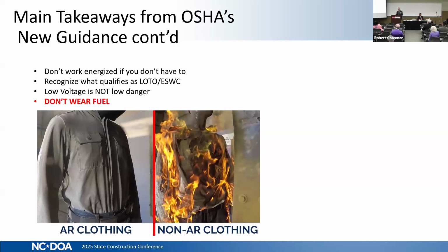So that's what you see on the slide. That's in the OSHA guidance. Every day, this should be daily wear for your workers that are working on electrical equipment: arc resistant clothing. And notice too, lockout, tagout, electrically safe working condition, right? In other words, just turning off equipment and putting a lockout tag on it is not sufficient anymore. You have to establish that condition.